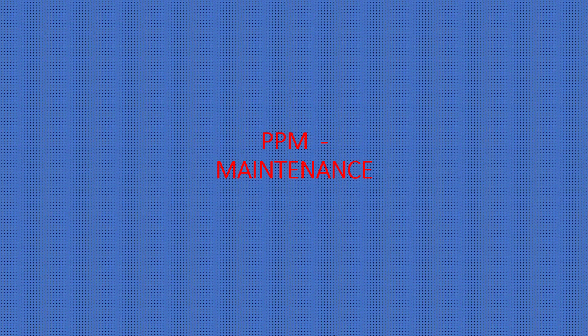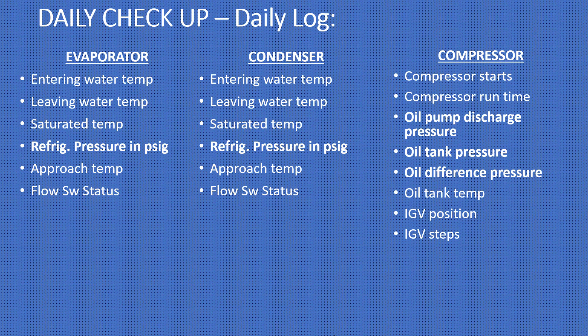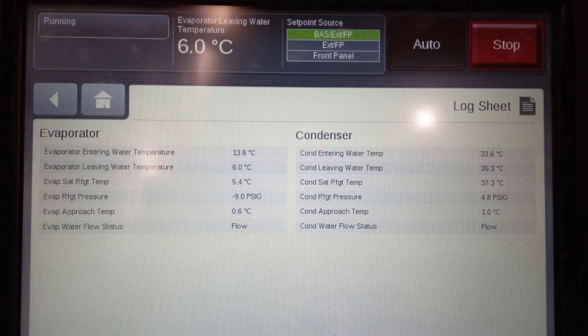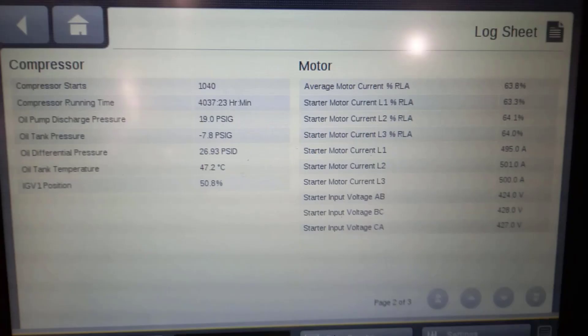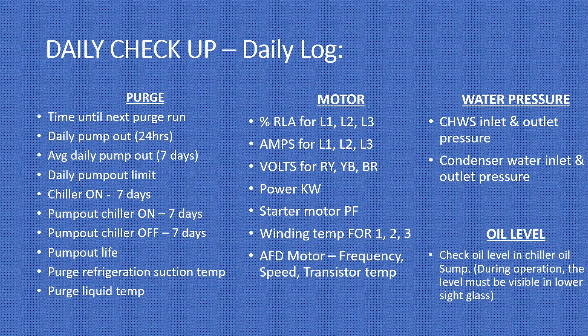For plant preventive maintenance daily checkup and daily log: start with the evaporator — check entering water temperature, leaving water temperature, saturated temperature, refrigerant pressure in PSIG, approach temperature, and flow switch status. Do the same for the condenser. For the compressor, check compressor starts, compressor runtime, oil pump discharge pressure, oil delta pressure, oil temperature, IGV position, and IGV steps. These are very important log items that HVAC technicians are supposed to check on a daily basis. You can get details for evaporator, condenser, compressor, purge, and motors — write them down and check against your daily log.